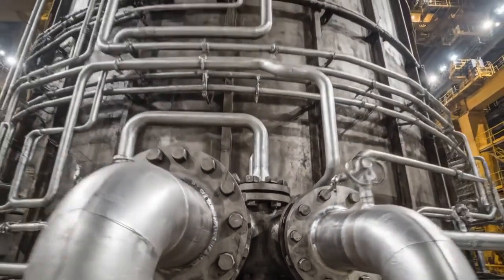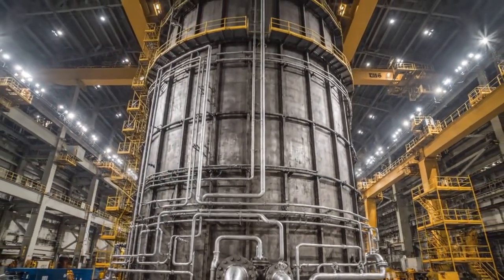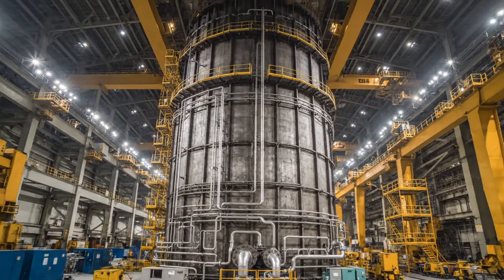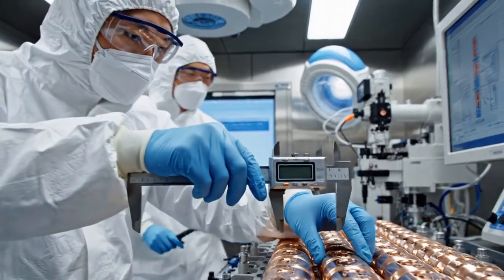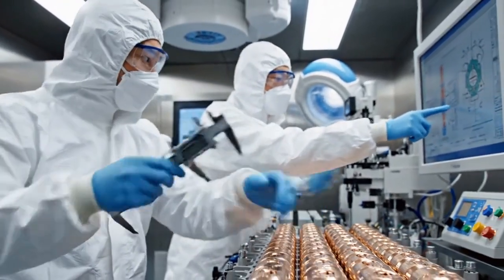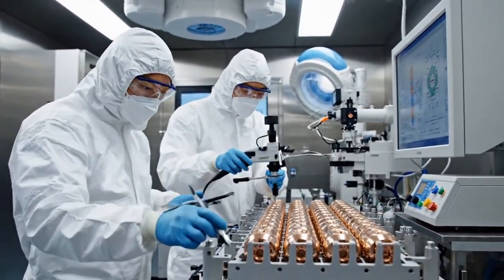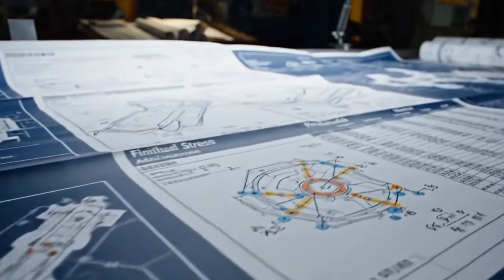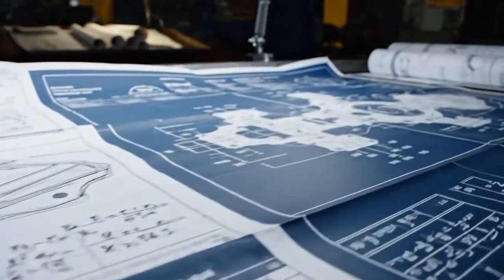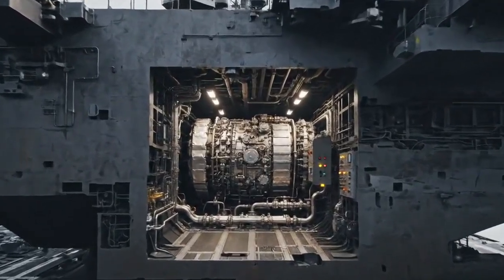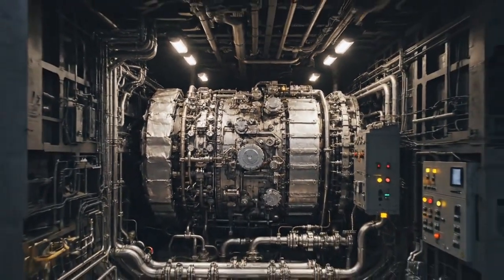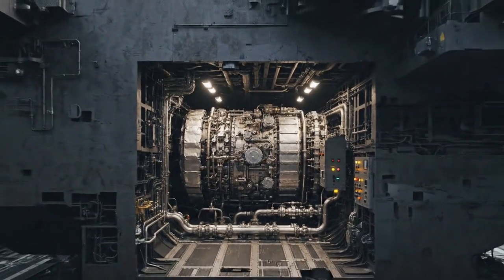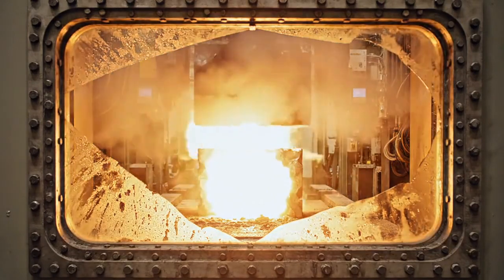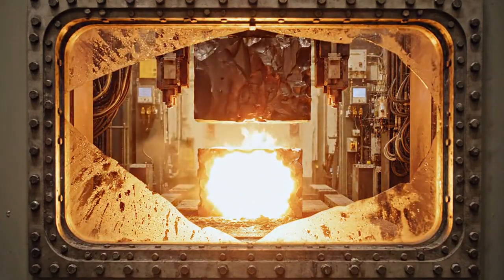To understand the sheer complexity of this machine, we must examine the fuel core anatomy. The fission process begins within the reactor pressure vessel, a cylindrical containment structure forged from specialized high-yield carbon steel. Inside this vessel lies the reactor core, comprising precisely arranged fuel assemblies. Unlike commercial civilian reactors, the A1B utilizes highly enriched uranium, or HEU. This weapons-grade enrichment level is a critical engineering calculation. By utilizing HEU, the physical size of the reactor core can be drastically reduced, saving critical weight and volume inside the ship's hull. However, containing highly enriched uranium undergoing continuous fission presents an extreme material science challenge.